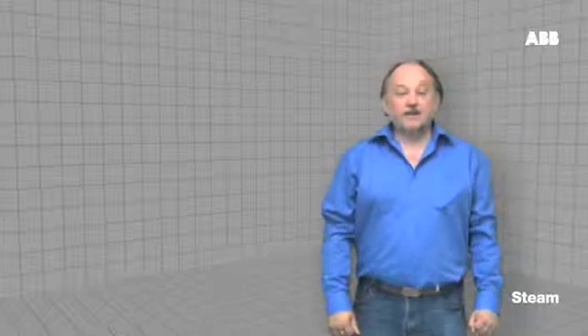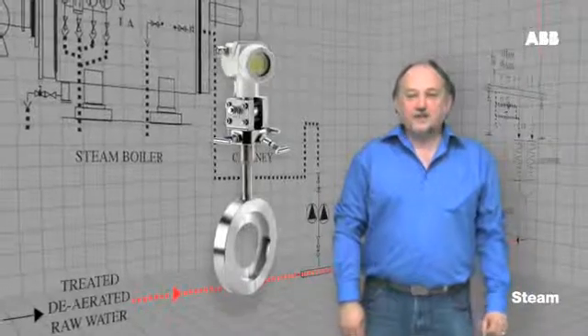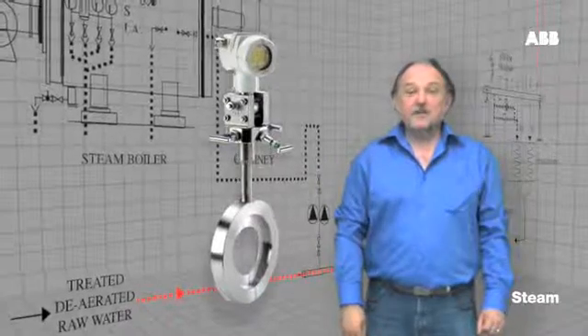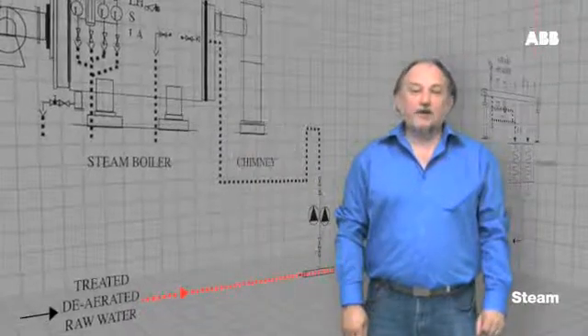Because the density and hence quality of your steam varies continuously, measurement in actual volumetric units of steam can be inaccurate. The key to accurate consistent measurement of steam system efficiency is to use mass flow measurement of your steam output and distribution to identify low efficiency boiler operation and plant areas and machines with poor leakage performance or reduced efficiencies.